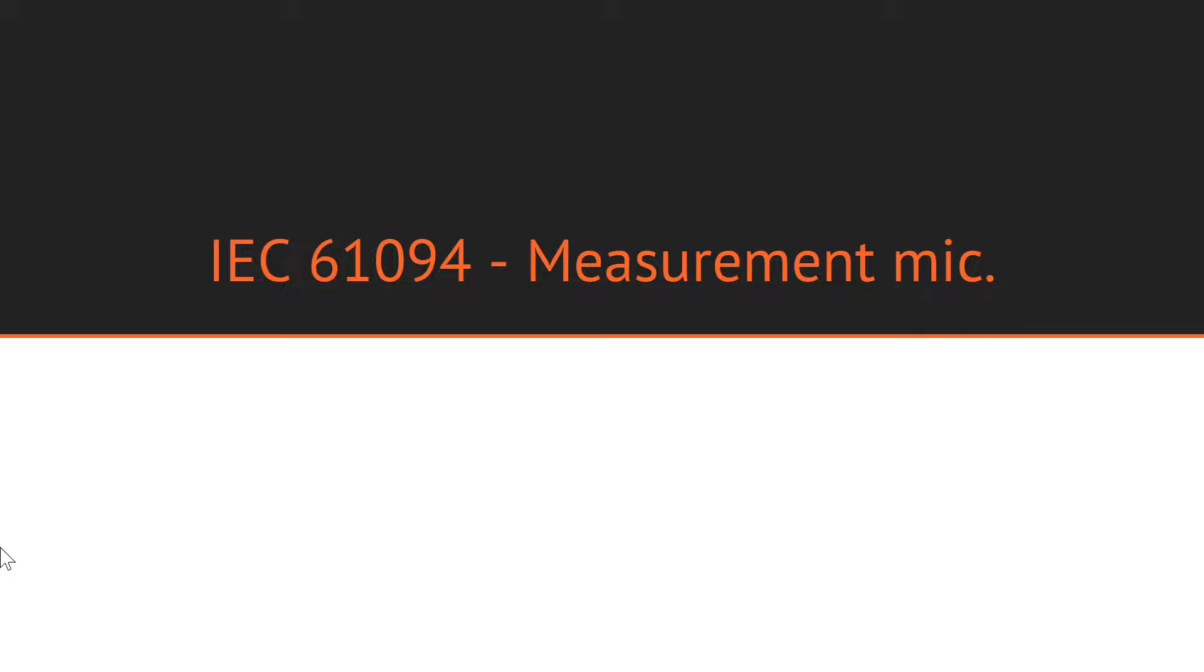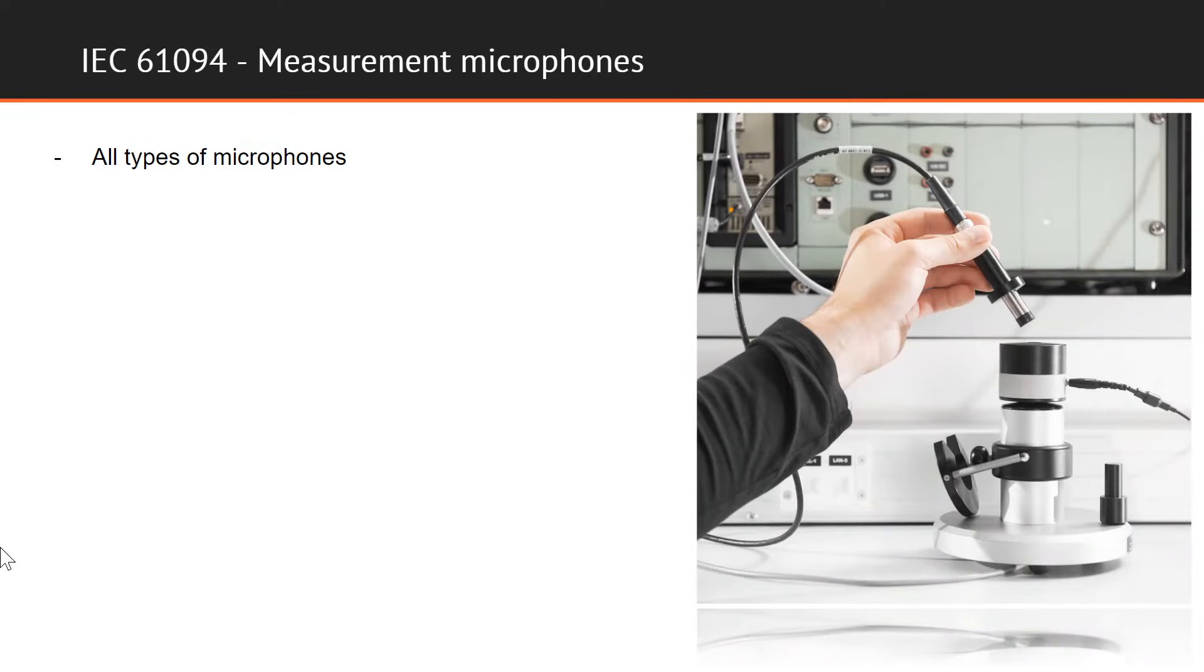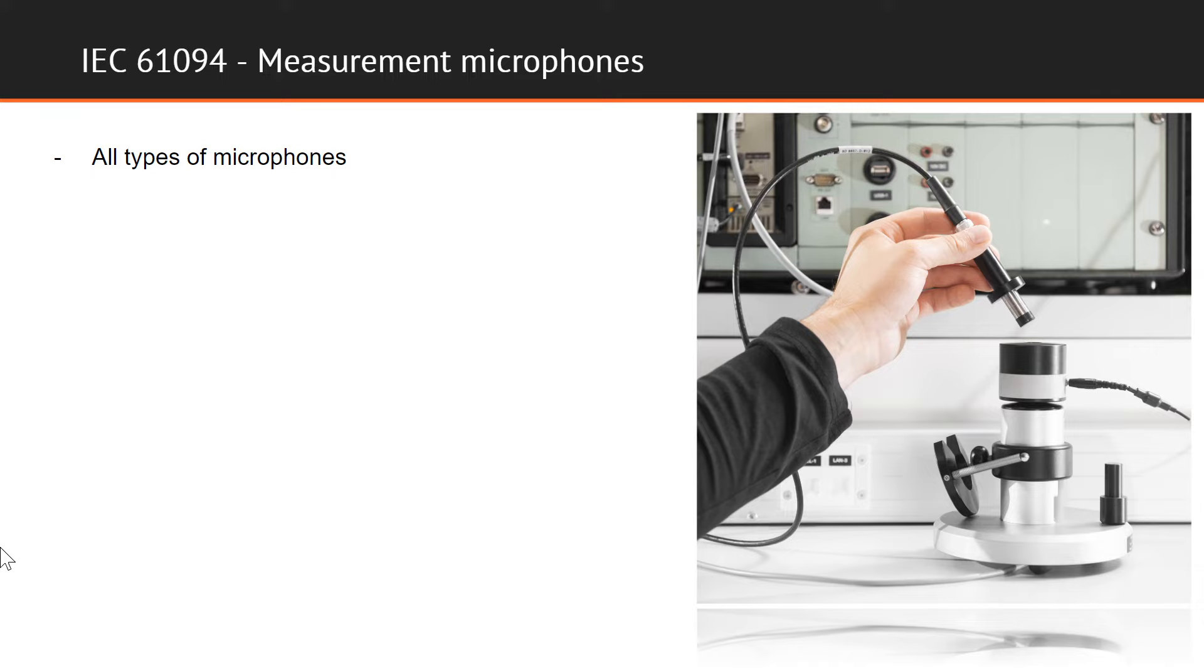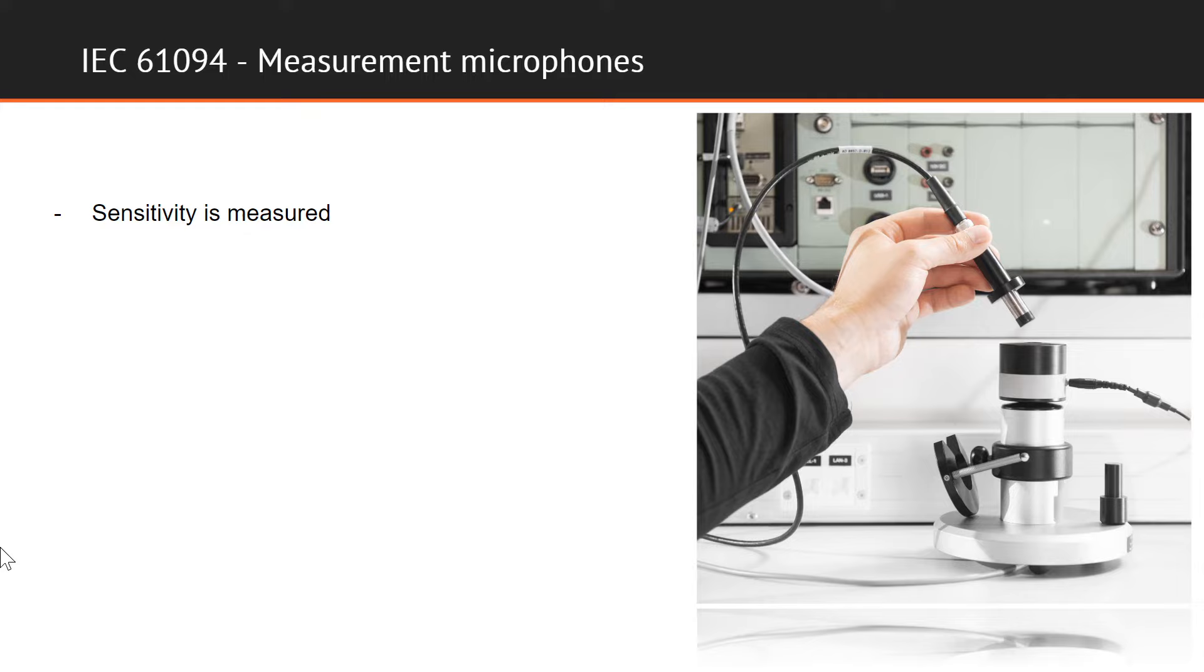In addition to before mentioned calibration of complete measurement chain, including microphone, cables, data acquisition unit, and the software part that can all be calibrated as class 1 sound level meter, separate calibration of the measurement microphone alone is often presumed. Such calibration of all types of microphones is performed according to IEC 61094, and this is true whether we are calibrating with or without preamplifiers.